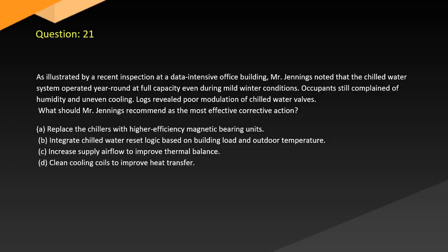Question 21. As illustrated by a recent inspection at a data-intensive office building, Jennings noted that the chilled water system operated year-round at full capacity even during mild winter conditions. Occupants still complained of humidity and uneven cooling. Logs revealed poor modulation of chilled water valves. What should Jennings recommend as the most effective corrective action?